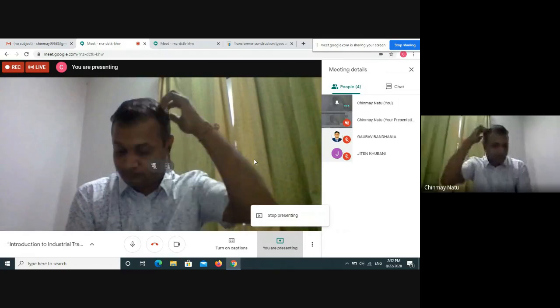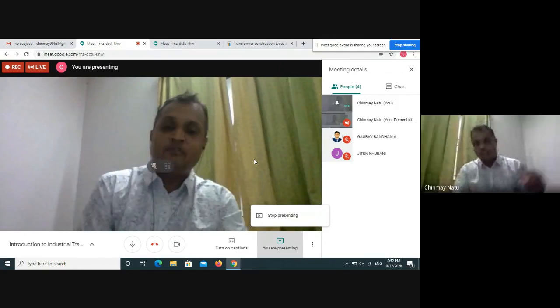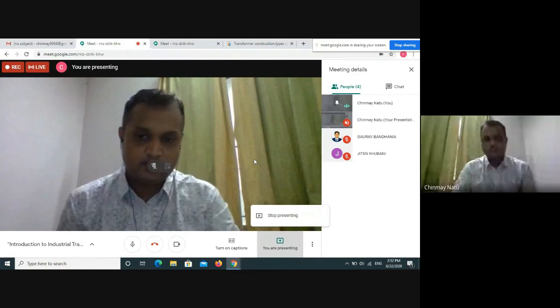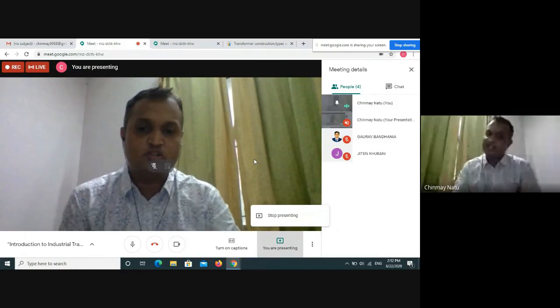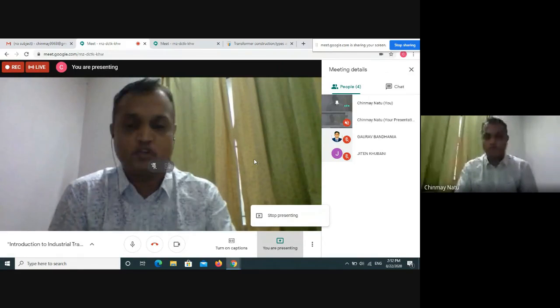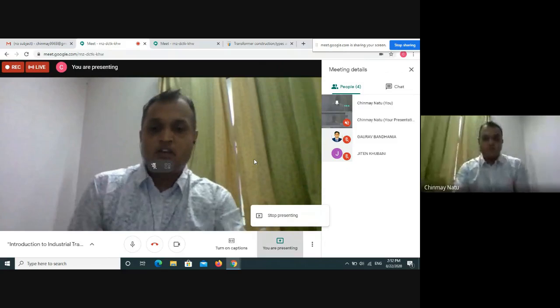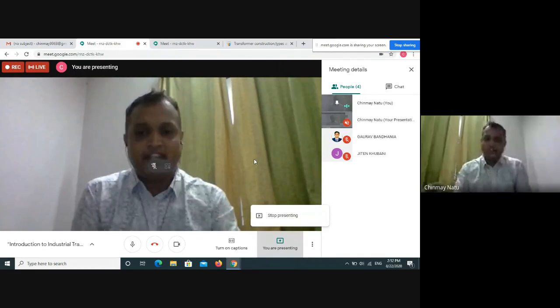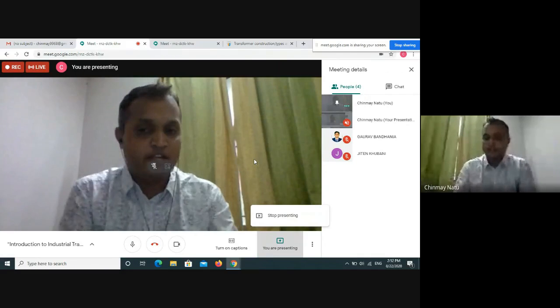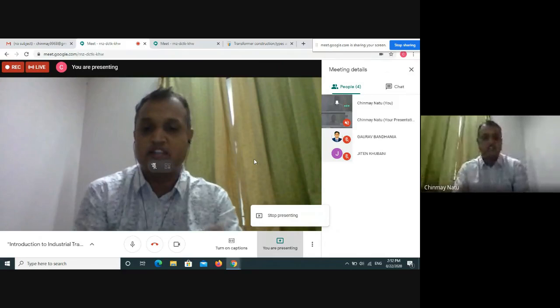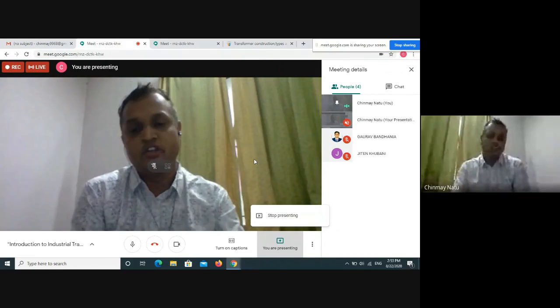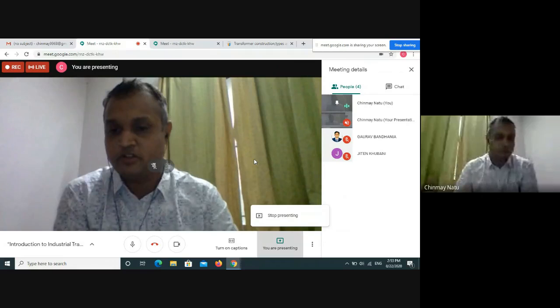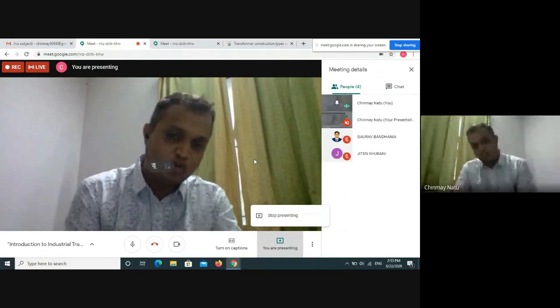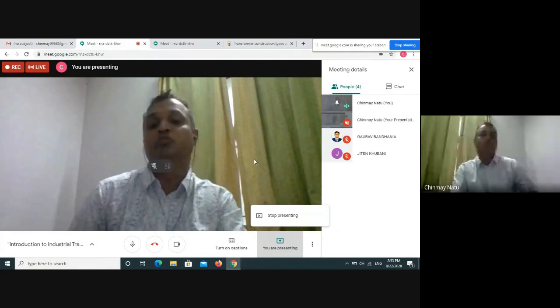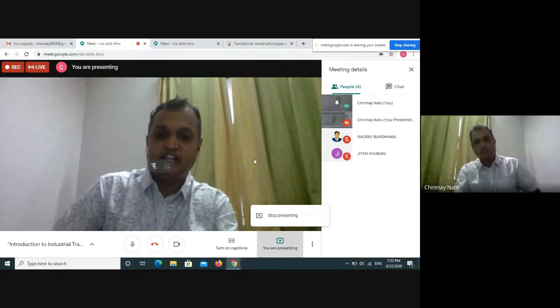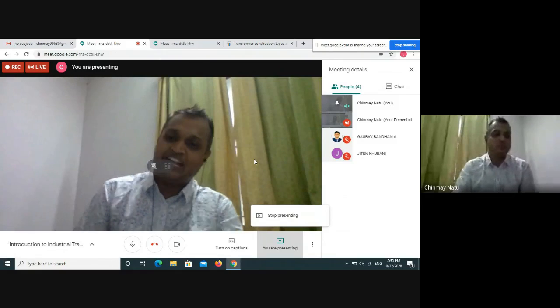I will explain. When voltage comes from the substation at 66 kV and output is 440V, if due to some reason the input voltage rises and output also rises, it will harm all our machines and cause damage. This is where the auto transformer comes in—it manages the output voltage irrespective of input voltage. This is known as an industrial transformer, or nowadays also as a servo stabilizer.